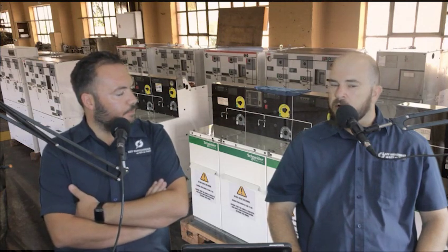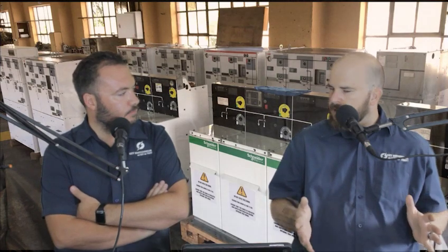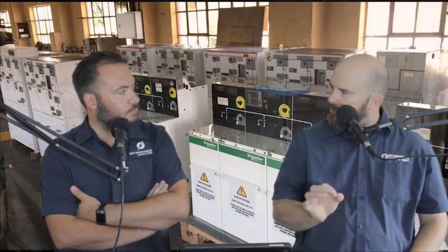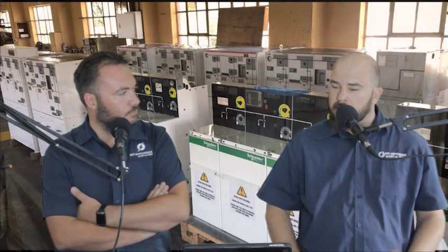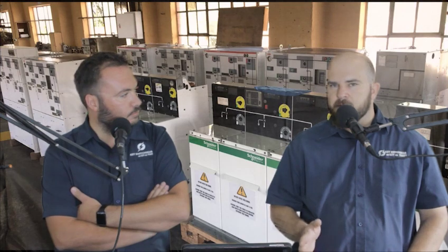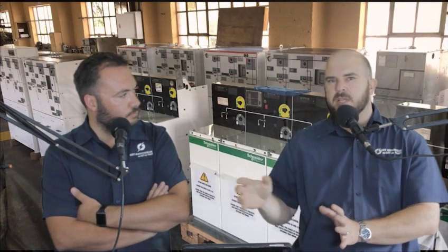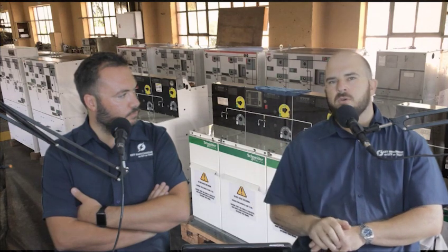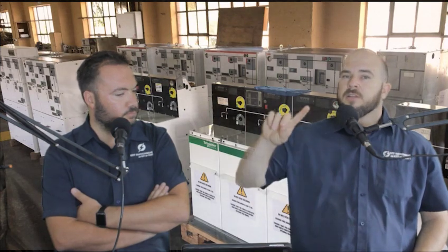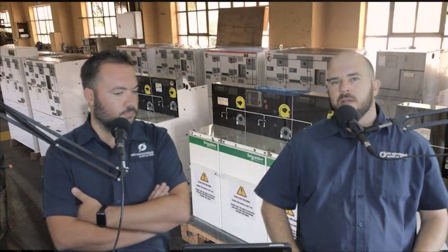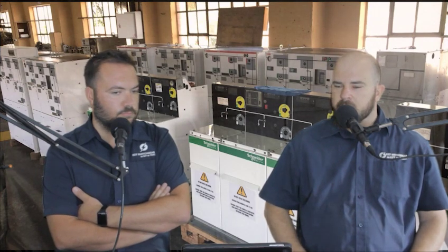Yeah, that's correct. Even in primary switchgear, you get gas insulated circuit breakers. They also have a gauge, a manometer, that shows you the pressure of the SF6 or whatever gas is used inside of that switchgear. In ring main units and secondary switchgear, you've got a manometer that will show you your SF6 pressure level, which should not drop below a certain level, and it should not be overcharged. That is something that just shows you the level of the insulation.